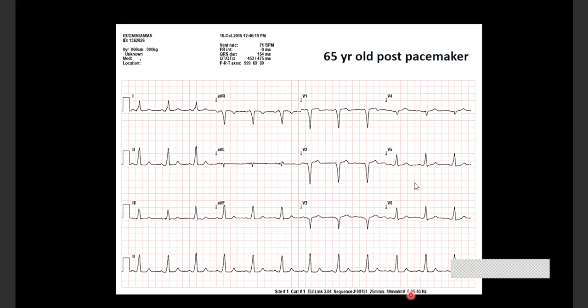So the patient's own breathing and all those things will cause a low frequency artifact, and that's why you sometimes get a drift in an ECG. The line will not be straight. The line will be going like this. That's called a drift artifact, because your high pass filter is set very, very low. It's picking up the patient's own breathing and other low frequency signals.